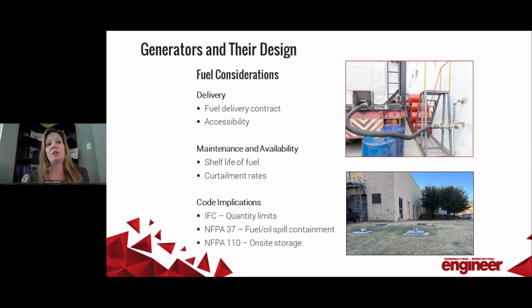That's not very much. Now, fortunately, there are footnotes in there that allow this capacity to be increased 100%, 2 times, if you have both a fully sprinklered building and the fuel is stored in an approved storage tank. You're allowed up to 360 gallons in the room. And then NFPA 37, as James mentioned, governs the amount of fuel that can be stored, but the IBC actually has stricter requirements here. So again, you've got to look at all of your codes and what your local jurisdiction is going to require. And then NFPA 110 also has distance limitations that you must maintain from the building. You can't have a fuel source any closer than 5 feet to a building.